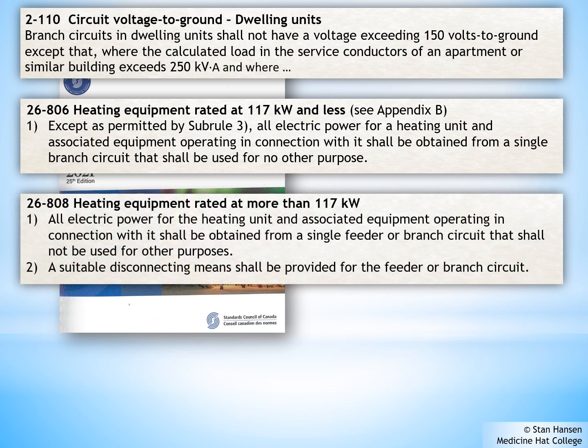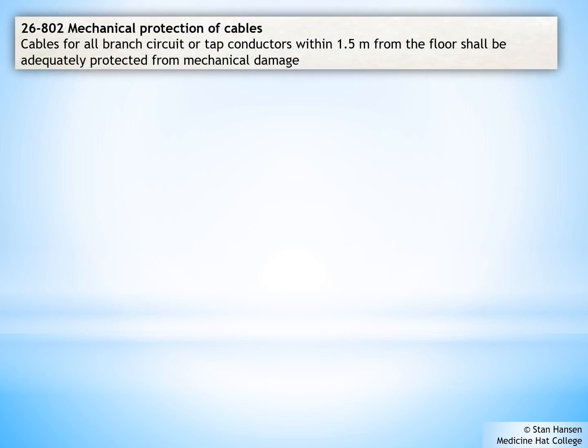26808 says that any electrical heating equipment rated at more than 117 kilowatts, which would be our electric heating, baseboard heating, and such things as that, they must all have their own branch circuit, and they're provided for only the heating equipment and their components. For any larger equipment, a suitable disconnect means is also required. Since my furnaces are typically mounted on a basement floor, I have to pay attention to Rule 26802, which speaks about the mechanical protection of conductors. My NMD90 is not armored, so therefore I cannot run it directly into the furnace. It will be below that 1.5 meter limitation. Instead, I'll do this section with an armored cable such as AC90 in order to protect my wires.